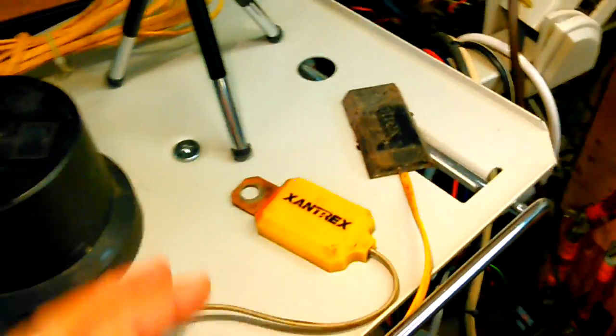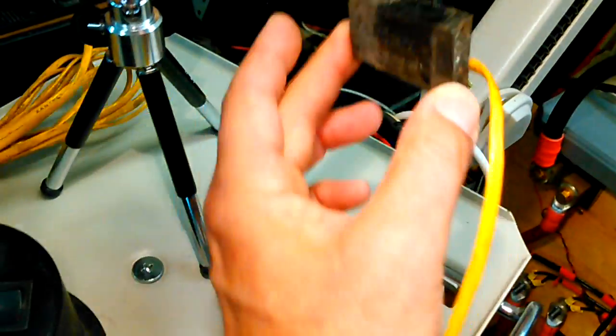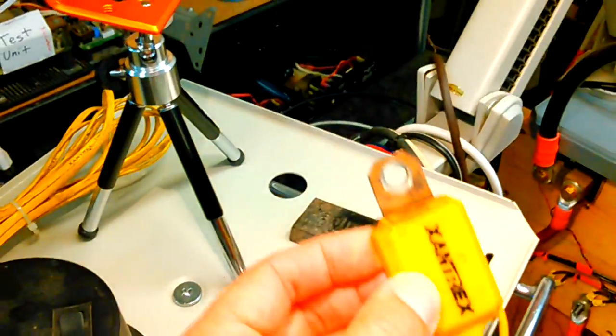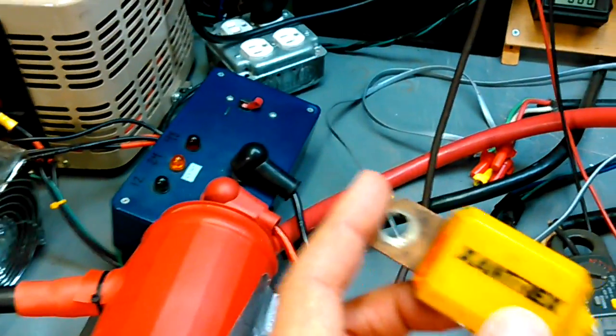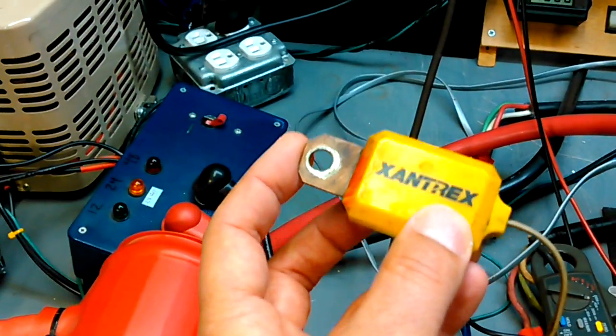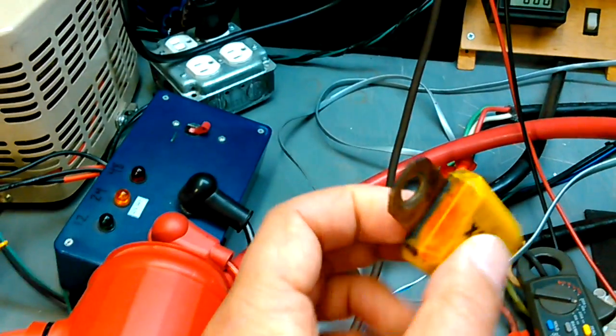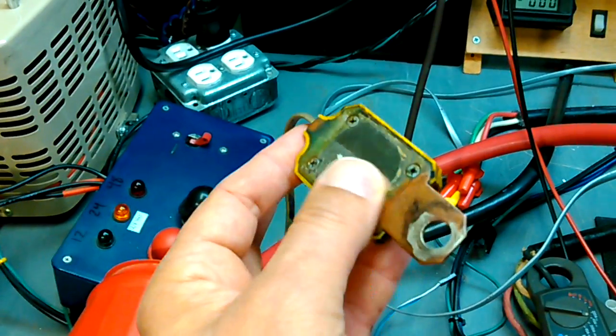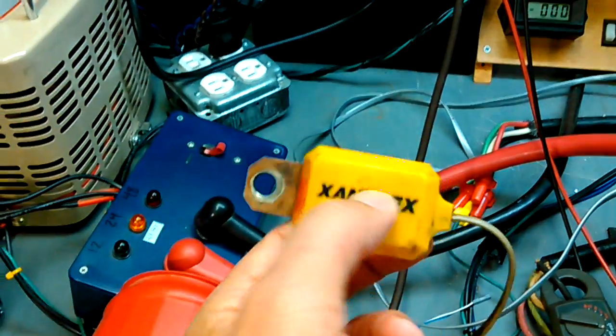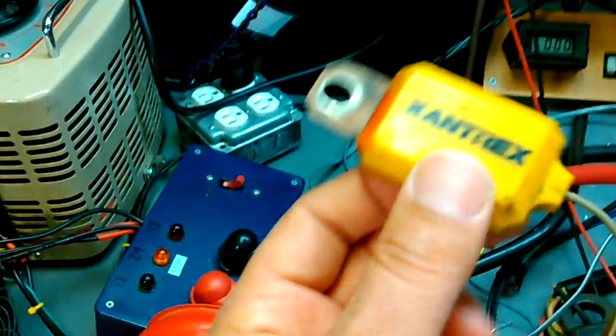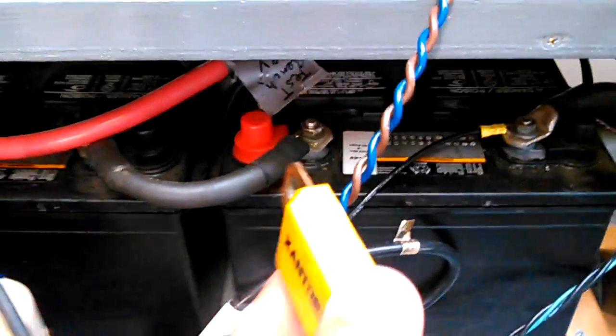Another note is, you notice this one, you just stick it on the side of the battery, and this one you actually have to bolt to something. What you need to know about this is that this metal tab doesn't electrically connect to anything. It's just a holder. The temperature gets transferred through this metal to the body, and then inside here the temperature sensor picks up that temperature. So I can bolt this to the negative, I can bolt it to the positive, doesn't matter. I can bolt it just somewhere in the battery compartment to pick up the temperature.